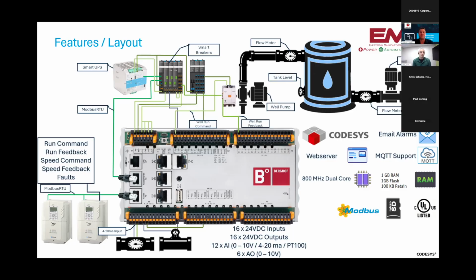And then you see in the upper left there, the smart UPS and the smart breakers. So this is really what starts setting us apart from some of the other pump controllers on the market. They'll give you a lot of features and a lot of functions, but it's still the same old thing. When you get out there in the field, you still have to use a Fluke meter. You still have to know what you're doing to be able to troubleshoot this. We've tried to make it easy so that before you drive to site, you know: do I have 120 volts coming in to my UPS? What is my battery usage? What's my discharge rate of my batteries? How long do I have before the batteries are going to go down?